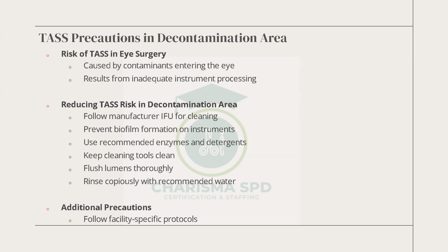Use recommended enzymes and detergents. Looking at the pH, it's going to be provided there for you. Keep cleaning tools clean and flush lumens thoroughly. Make sure you're pumping water through these lumens, through these channels, to clean them at the most you can, with the brushes, and then rinse copiously with recommended water. We've told you about the water and the contaminants and everything. You've got to make good work of that. Any questions here?